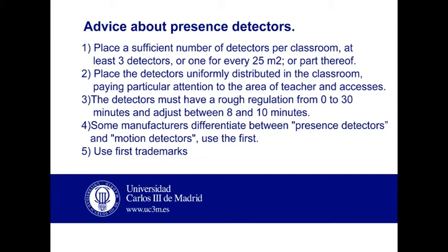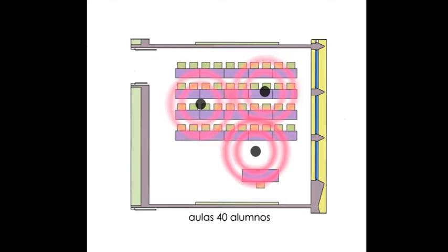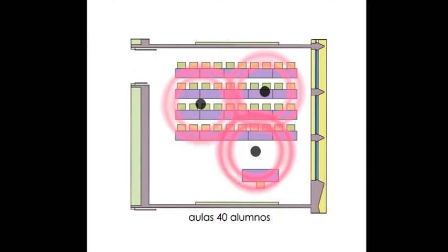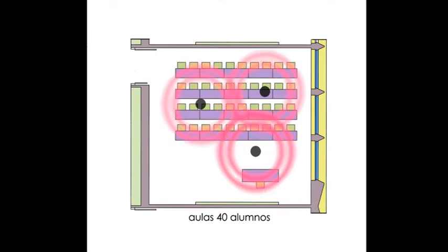4. Differentiate between presence detectors and motion detectors. Use the first. 5. Use first trademarks. When positioning the detectors, always put one near the place of the professor. The rest should be uniformly distributed. Check that the scope covers all the classroom.